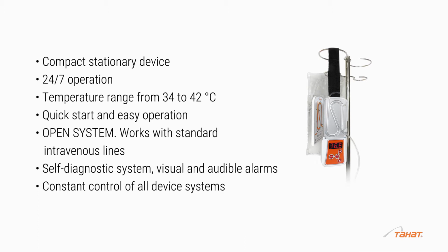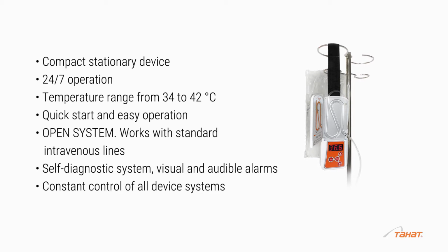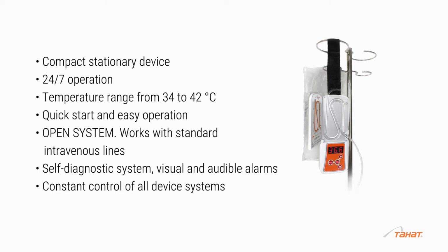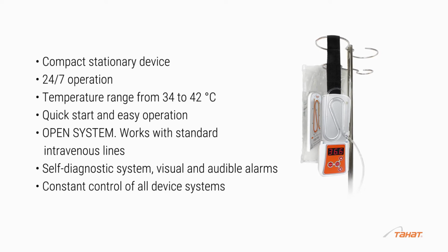Compact stationary device, 24/7 operation. Temperature range from 34 to 42 degrees Celsius. Quick start and easy operation. Open system. Works with standard intravenous lines. Self-diagnostic system, visual and audible alarms. Constant control of all device systems.